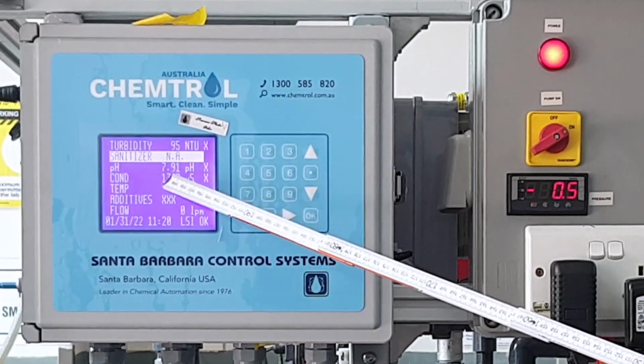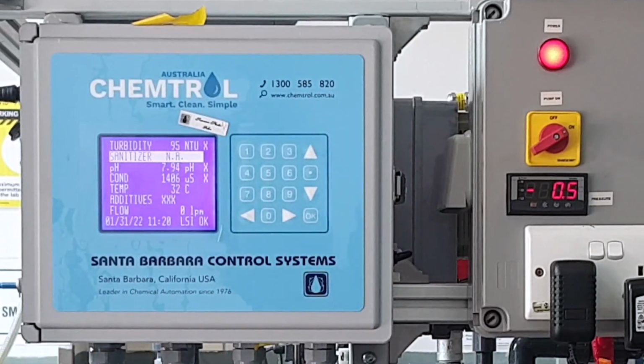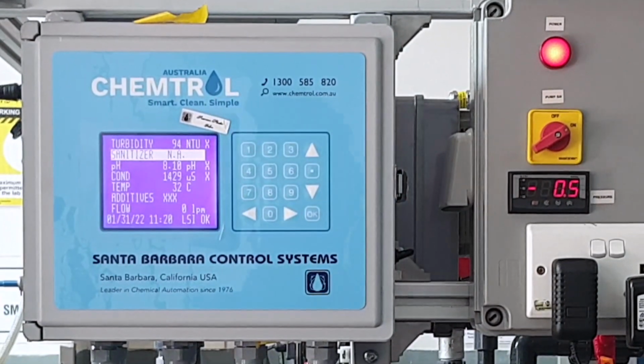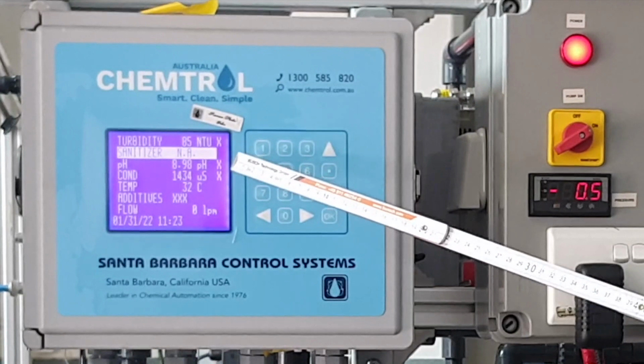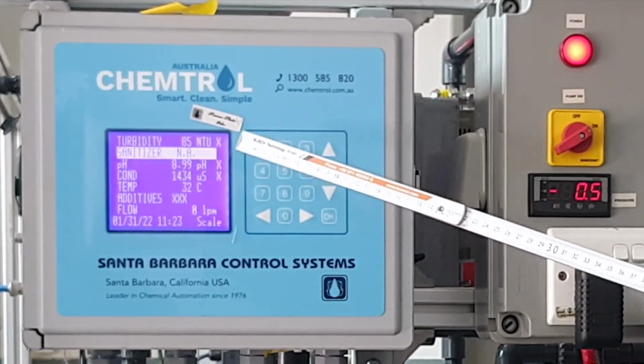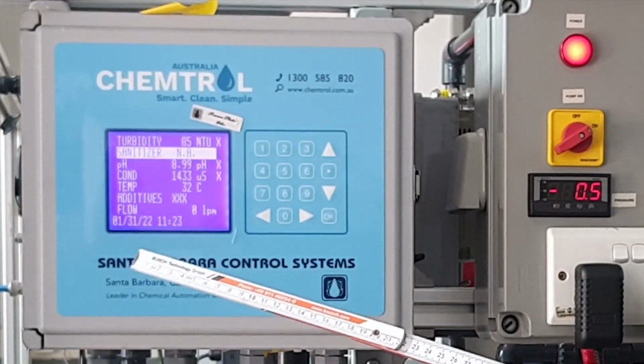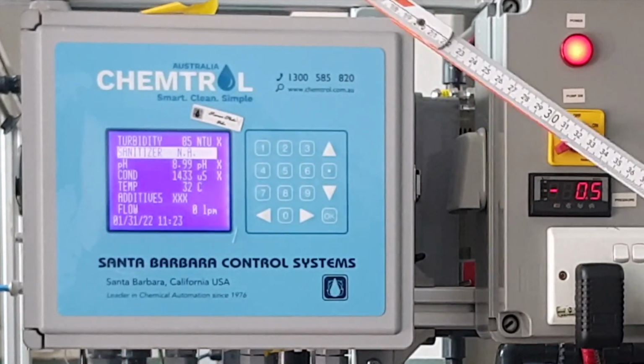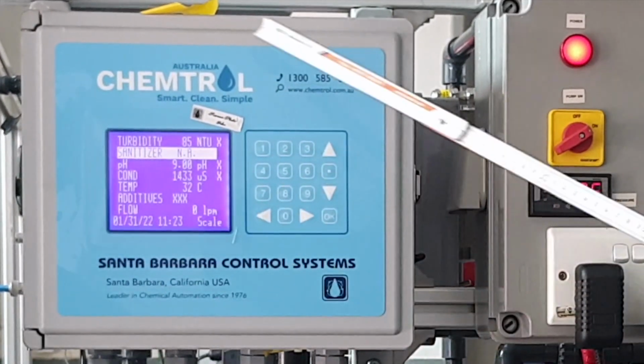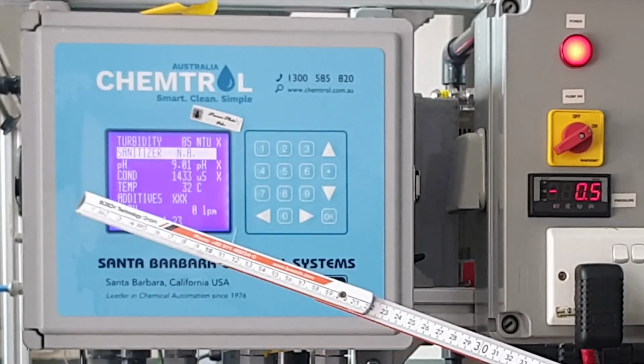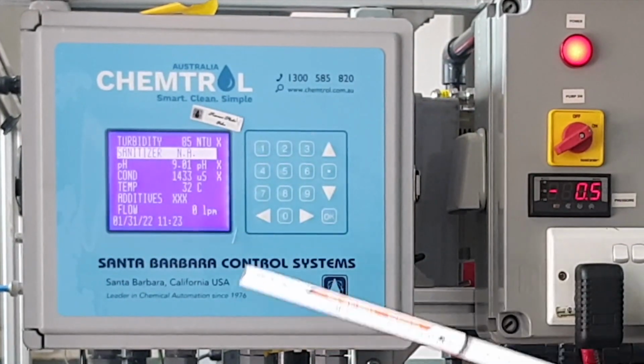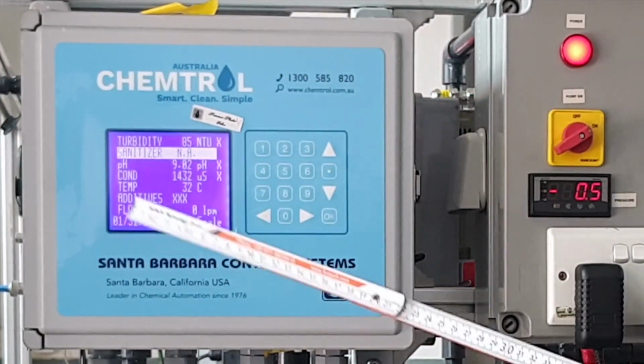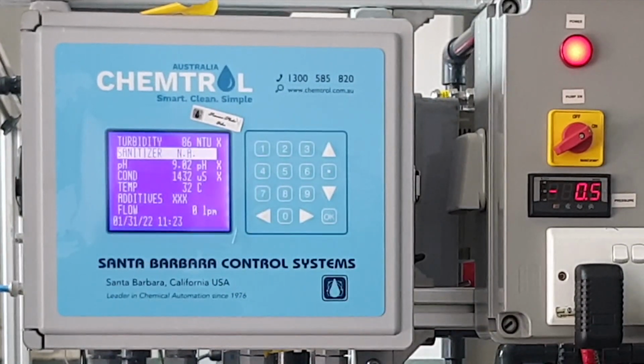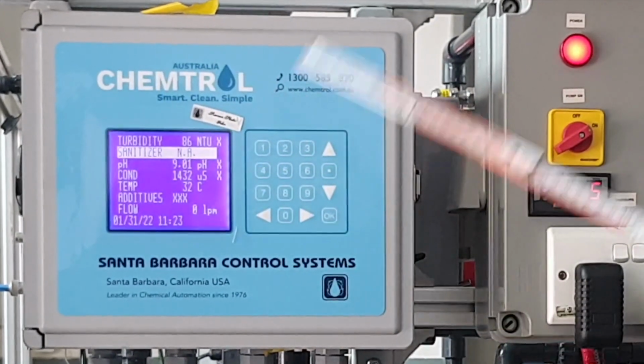This allows us to take the water pH to 8 or more, which is safe to discharge to the ocean. So the pH has now risen to 9, which allows us to use calcium carbonate and magnesium carbonate and/or magnesium hydroxide to control the overall pH in the system for discharge. This allows a large amount of bicarbonate to be loaded up into the system before it's diluted and transferred out to the ocean.